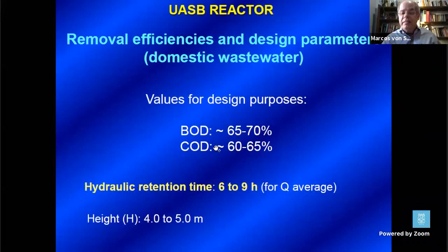Typical removal efficiencies are not high, as I had told you. So they are around 60-70% in terms of BOD and COD, but they are very compact. They are designed for domestic wastewater based on hydraulic retention time. Under our climatic conditions, something between 6 to 9 hours. So on average, I would say 8 hours. So they are very compact reactors. These are the typical heights between 4 and 5 meters. Okay.